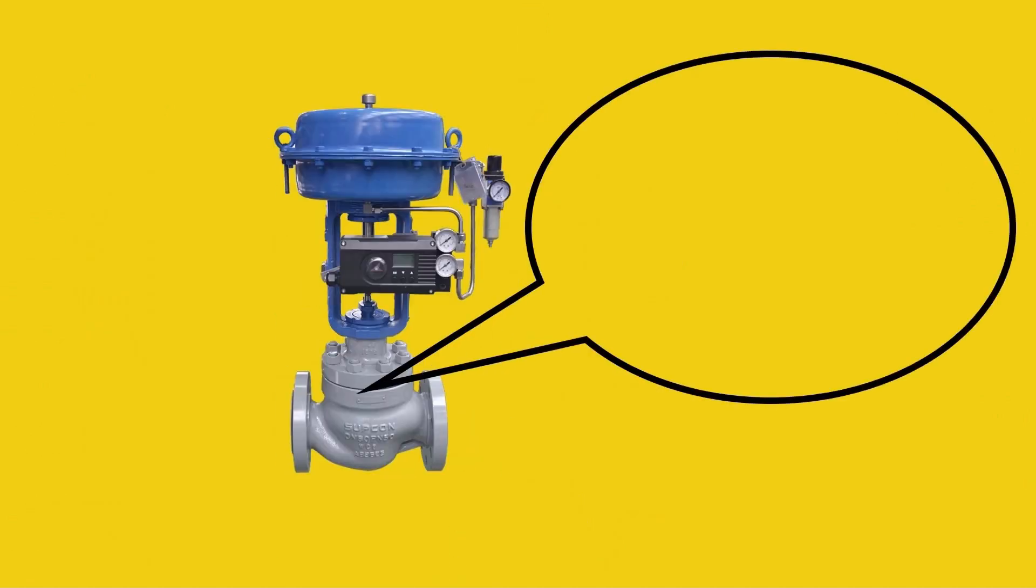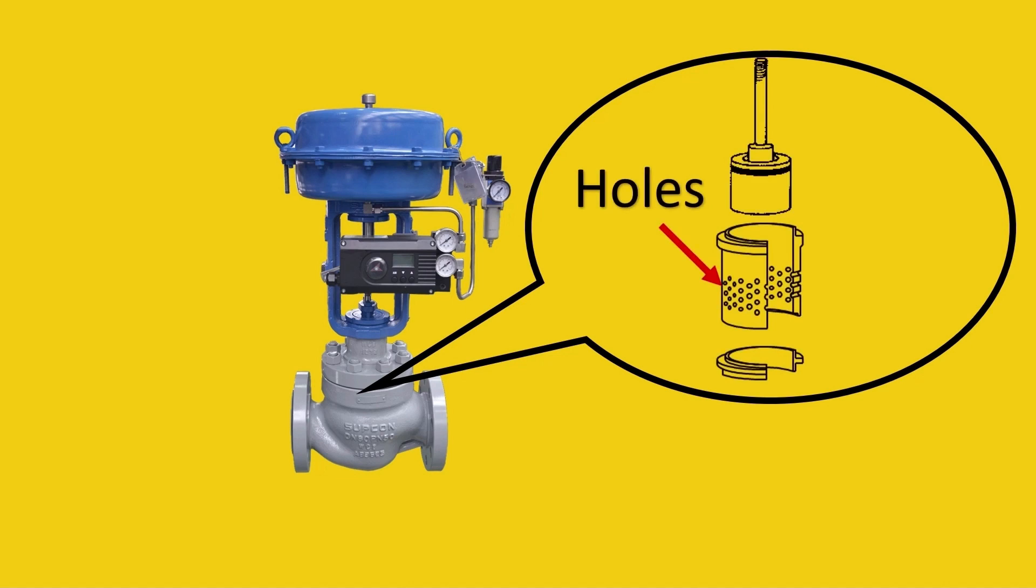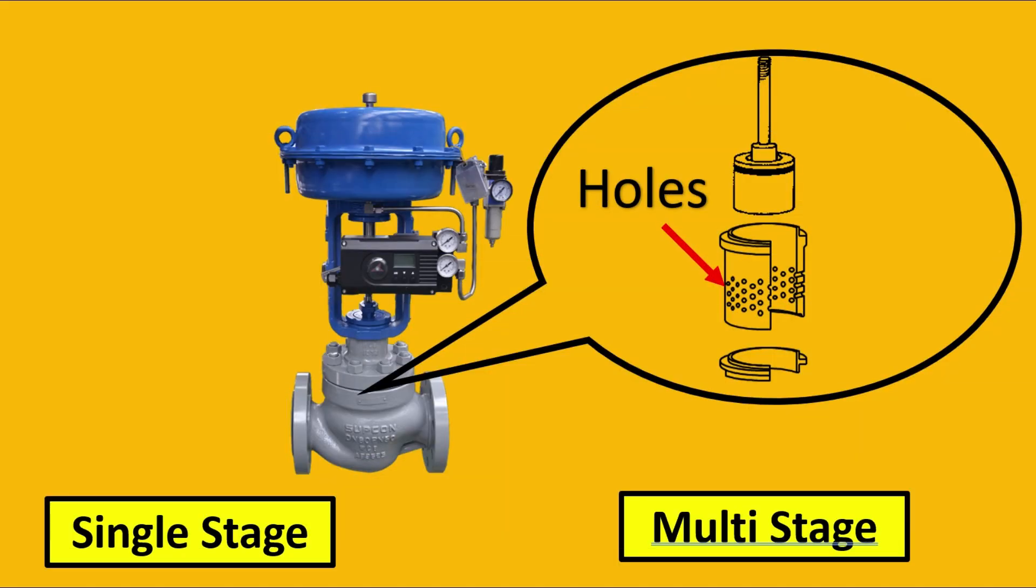There are some special kind of valves that are made. What they do inside the valve is in the trim, they make holes into it, so that the pressure drop will happen eventually. And then something was born which is called a single stage trim and multi-stage trim. Depending upon how severe is the cavitation, we either have single stage trim or multi-stage trim.